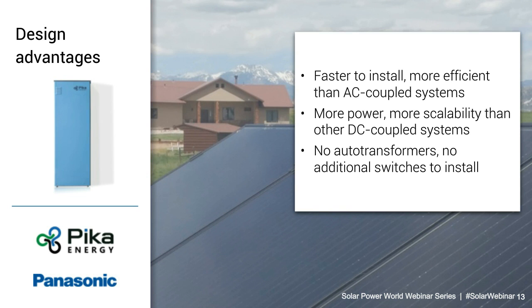And versus other DC coupled systems, this one provides more power and more scalability. So really another design advantage around, especially backup power, if you're trying to use it for providing bigger loads when you're islanding, that's a huge advantage here. And without the auto transformer or additional switches to install, it's just a cleaner, simpler installation. Really helps to reduce the soft costs for the integrator in putting the system together. That way you're not stuck for days on end trying to get the whole project done. We really look at battery systems as products and not projects. This is kind of a new world we're in where smart batteries can be installed as easily as inverters.